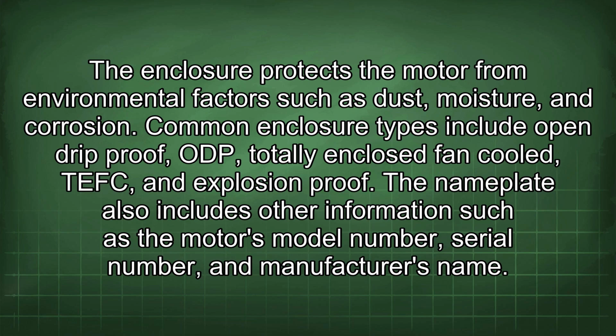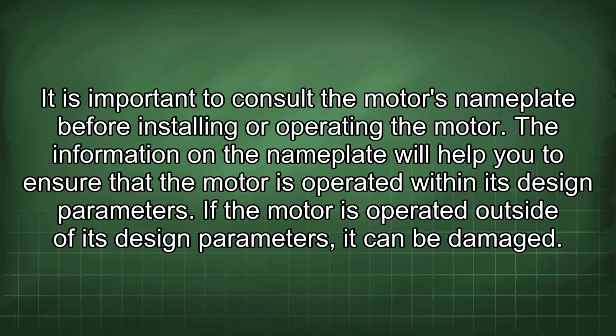The nameplate also includes other information such as the motor's model number, serial number, and manufacturer's name. It is important to consult the motor's nameplate before installing or operating the motor. The information on the nameplate will help you to ensure that the motor is operated within its design parameters. If the motor is operated outside of its design parameters, it can be damaged.